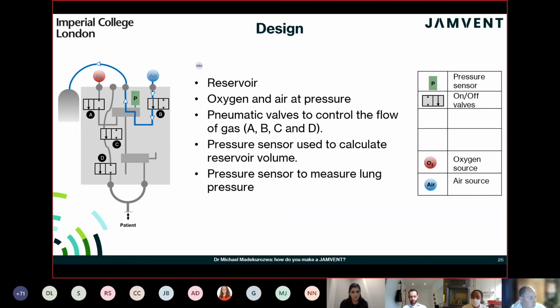The pressure sensor, there's another pressure sensor inside the system, and that's down over here, which measures the pressure inside the lung. So this is for clinical use because it's good for the clinician to be able to see what's actually going on inside the lung. And it's also as a safety mechanism. So if the pressure inside the lung goes high, the system will detect it and act accordingly in order to decrease the pressure.